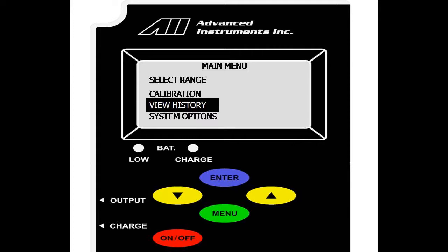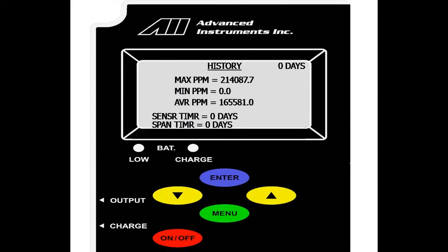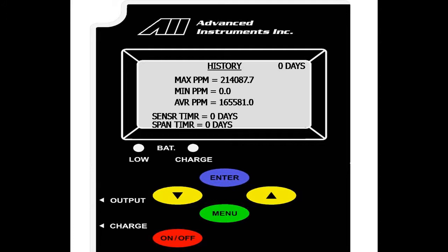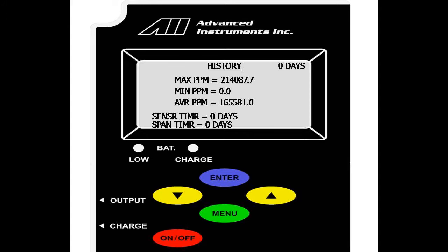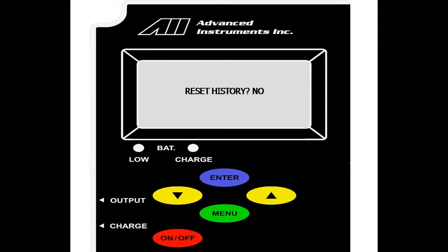We will now go over the view history option on the main menu. Scroll down and select enter. On the view history menu, you can see the max PPM, the min PPM and the average PPM of the current sensor installed. This history is reset every time a new sensor is installed. You also have a sensor timer and a span timer. This shows the amount of time the sensor has been in service and the amount of days that the sensor has last been spanned. Again, this history is reset every time a new sensor is installed or it can be reset by the user by hitting enter on the view history menu as seen here.